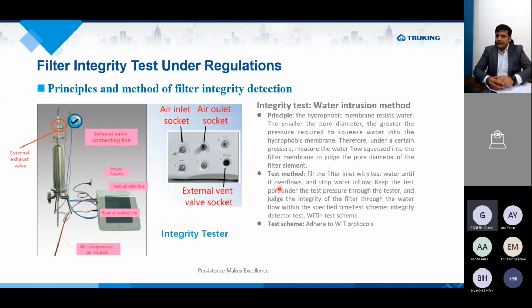So for filter integrity testing under regulation, we can have a certain set of procedures named the water intrusion method. On the left side, you can see the equipment which is connected to the filter with the housing in line. It has a particular valve for exhaust. It has power supply lines. Then these are the air inlet line and the air outlet line. The air compression source is connected to the device which is used for the intrusion test. And these are the inlet and outlet sockets of the tester itself.